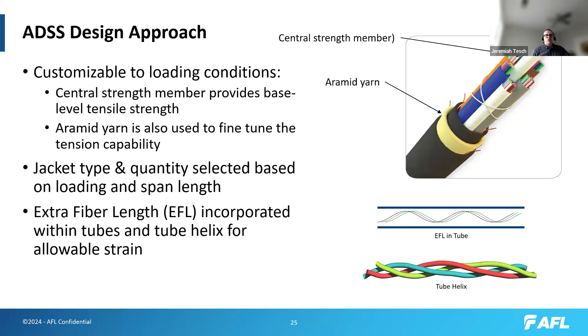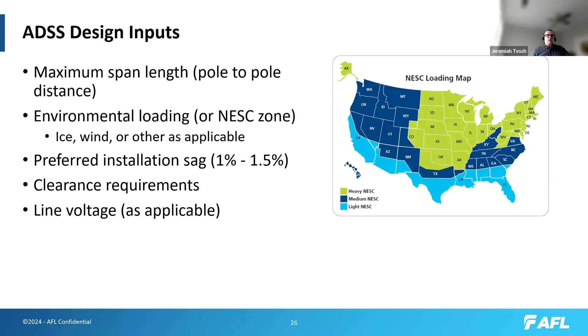Typically for the US, we use the NESC zones, so light, medium, and heavy, and those incorporate ice, wind, and a certain level of safety factor as well. And then you also have a preferred installation sag, typically 1% to 1.5%, any ground clearance requirements, line voltages, and that sort of thing. And just kind of illustrate the spans here and the sag.